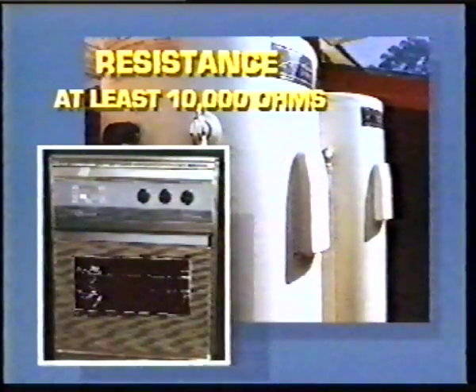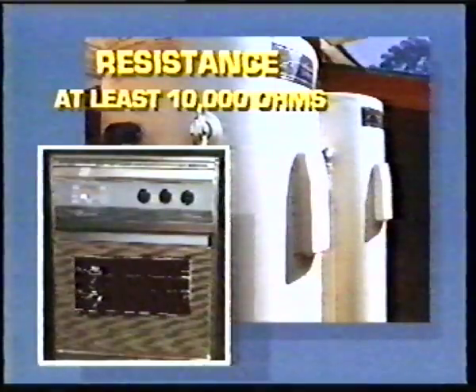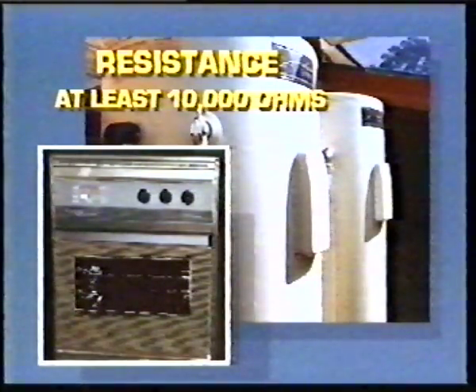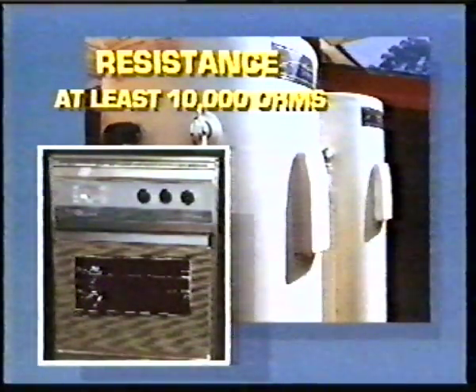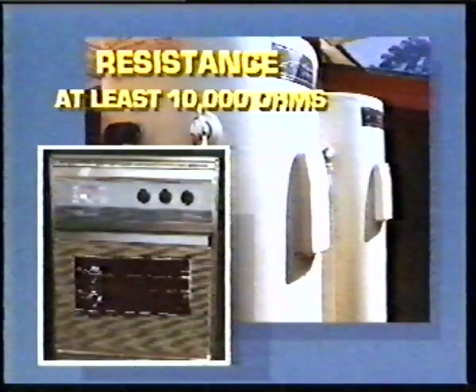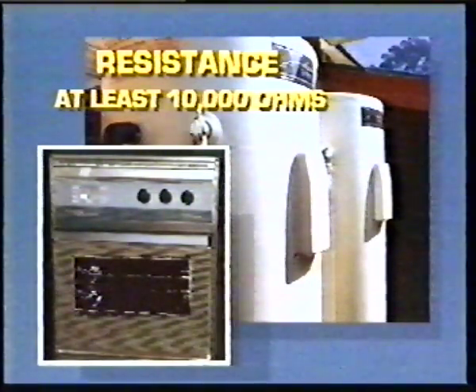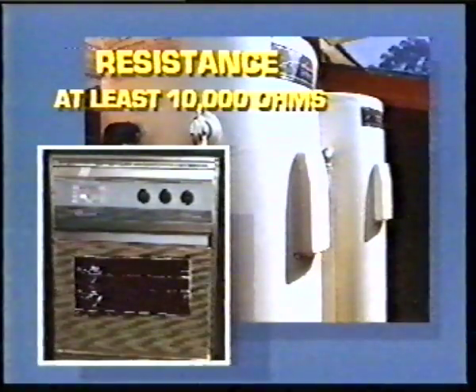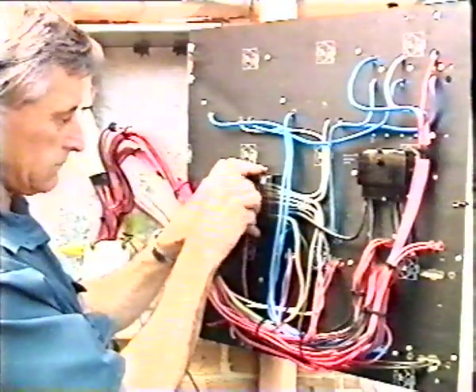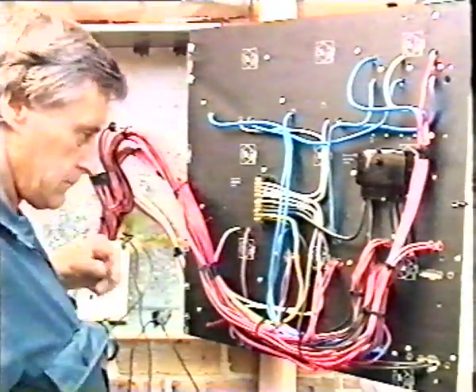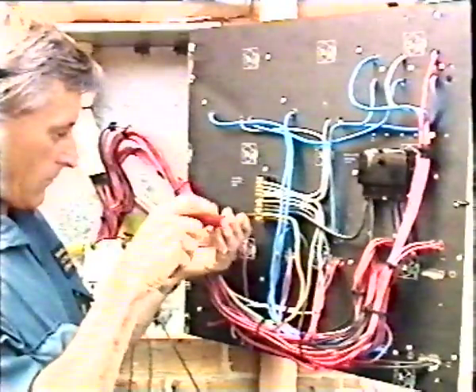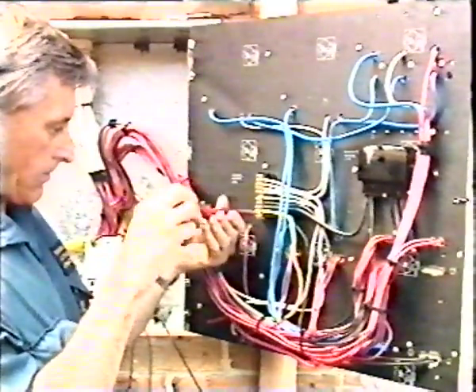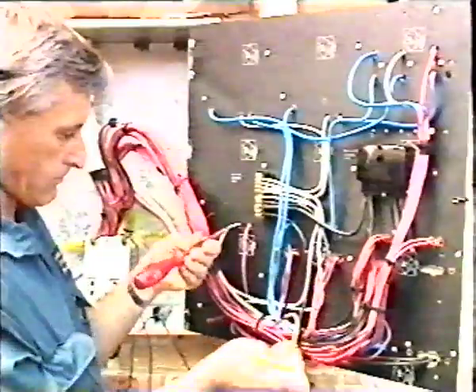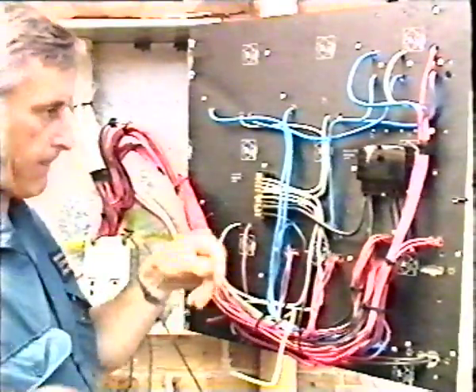This may be reduced for appliances containing heating elements which may have been subjected to moisture absorption, such as water heaters or ranges, provided that a resistance of at least 10,000 ohms is obtained for the appliance as a whole. For the test, we need an insulation resistance tester. The test should generally be performed on the installation as a whole, that is, by connecting all live conductors together, or in component parts by individual submains, final subcircuits, or items of equipment.